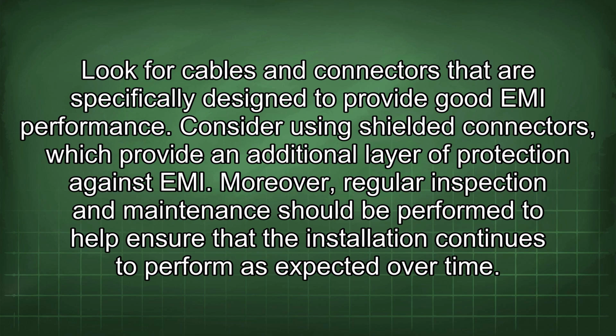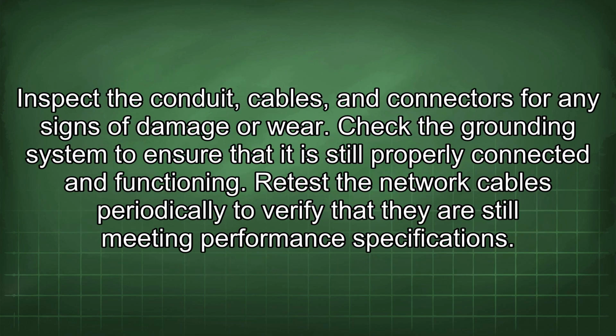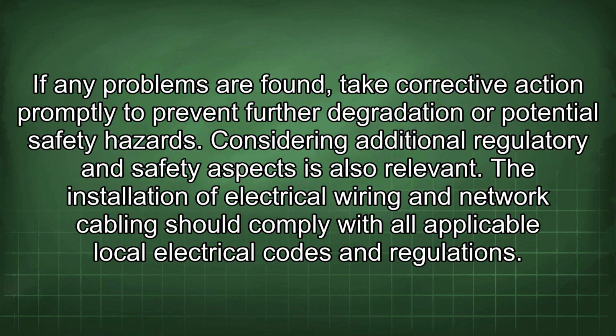Moreover, regular inspection and maintenance should be performed to help ensure that the installation continues to perform as expected over time. Inspect the conduit, cables, and connectors for any signs of damage or wear. Check the grounding system to ensure that it is still properly connected and functioning. Retest the network cables periodically to verify that they are still meeting performance specifications. If any problems are found, take corrective action promptly to prevent further degradation or potential safety hazards.